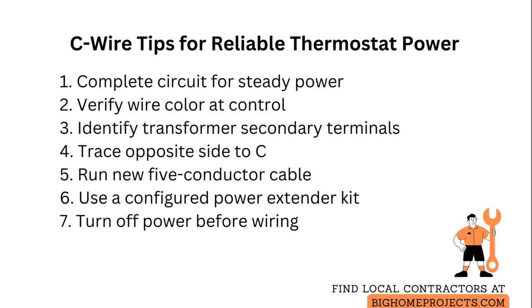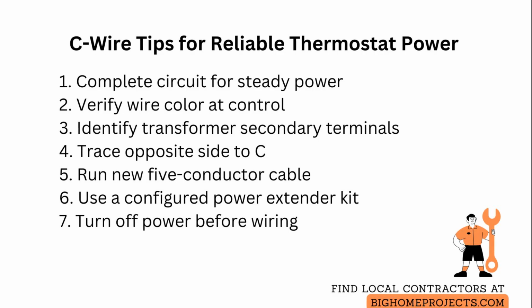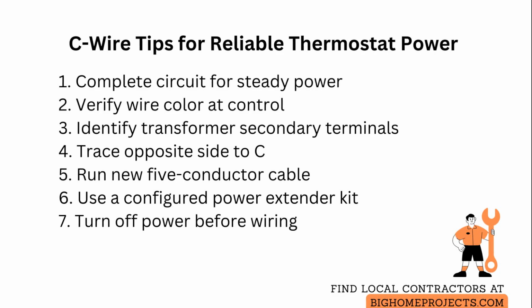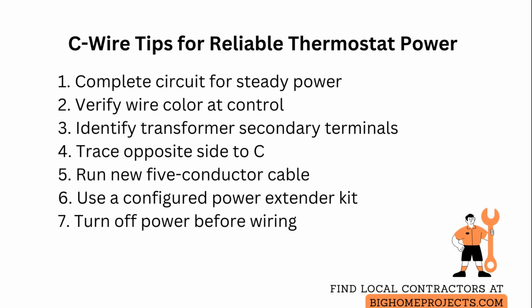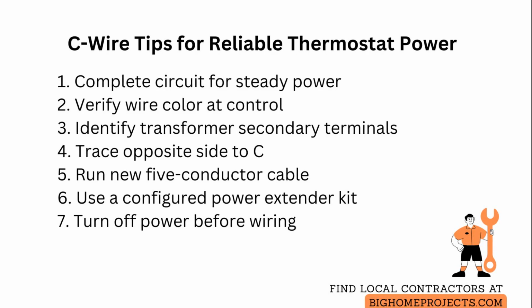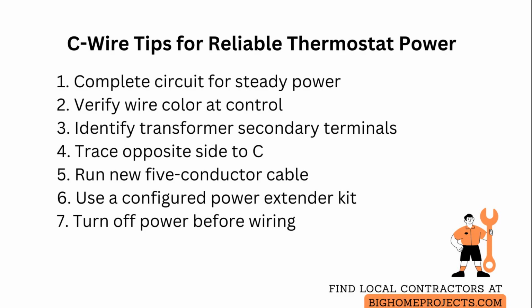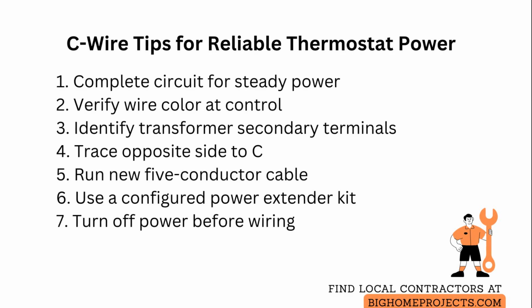For older homes that only have 4 conductor cable, the reliable fix is to run a new 5-conductor cable between the thermostat and air handler, or use a professionally configured power extender kit that safely supplies a C equivalent without compromising control signals. When adding a wire, turn off all power at the service switch, label each conductor, and secure connections under the correct screw terminals to avoid stray shorts or miswiring.